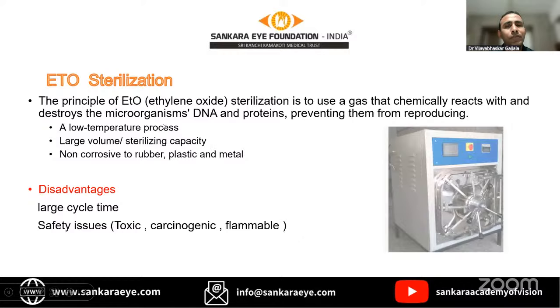The gas that we are using as a sterilizing agent is ethylene oxide. It is an alkylating agent. When it is exposed to microorganisms, it chemically reacts and destroys these microorganisms' DNA and proteins, preventing them from reproducing. Unlike autoclave sterilization, it is a low temperature process where usually the temperature will not exceed 60 degrees centigrade. The main advantage is that we can put a large volume of packs inside the ETO chamber, so the sterilization capacity is very high. And one more thing is it is non-corrosive to different materials like rubber, plastic, and metal products.